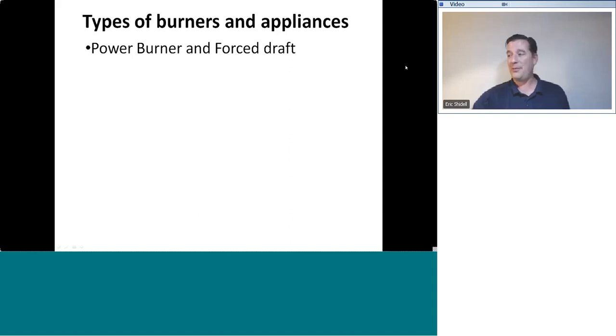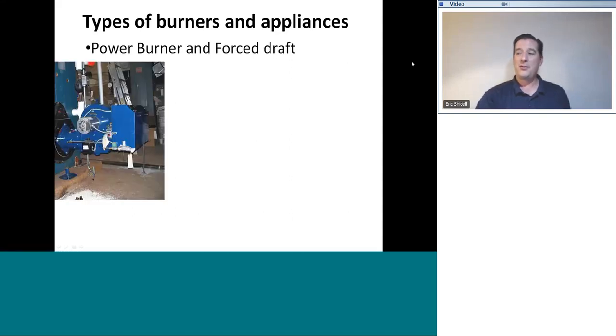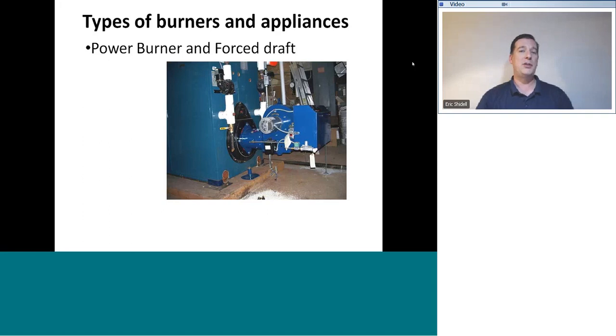Power burners are similar to oil burners. So if you're in a very big oil market, you know about power burners. It's very much the same thing. But instead of oil as the fuel, it is gas as the fuel. In fact, a lot of larger power burners are designed to operate on both a liquid fuel and a gas fuel. They're called dual fuel burners, pretty neat. You'll find them in a hospital or something. If there is a natural disaster and the gas supply is cut off, they've got fuel oil in reserve and they can continue running.